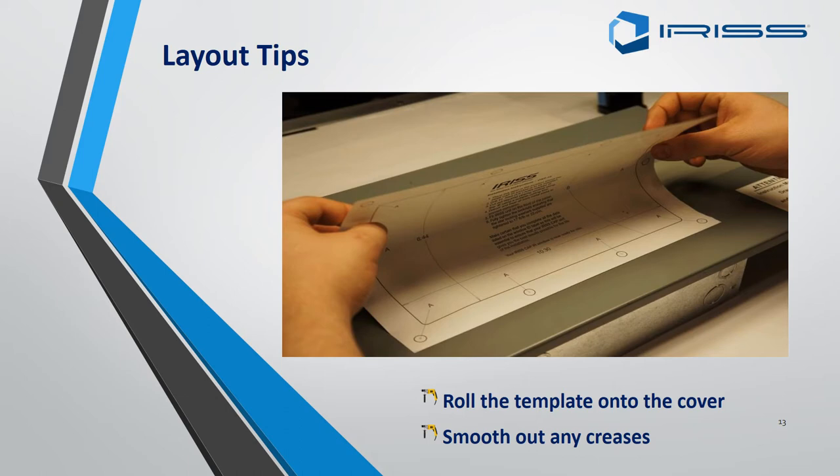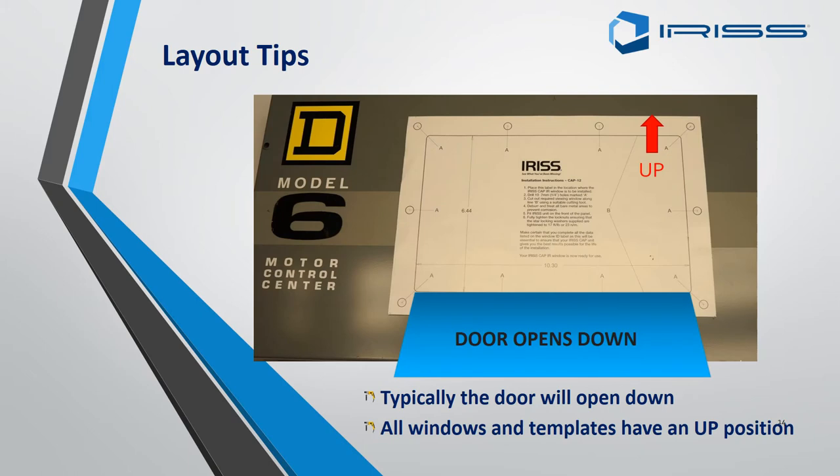When fitting an MCC with a cover, be aware that normally the door opens downwards. You can fit MCCs vertically so the door opens to the side, but the rule of thumb is that this style of MCC is fitted horizontally so the door opens downwards. There is a small T and B on the template indicating the top and the bottom.